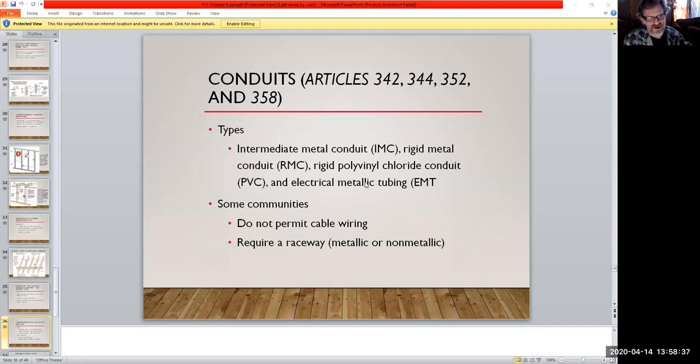And then there's a formula that we can use for tubings and raceways and even boxes, because you're going to get situations where you mix and match, where you might have number 12 and number 14 both going through this tubing or raceway. So you can calculate through and figure out, okay, I'm allowed this much and this much, and that's how much we can push through here.